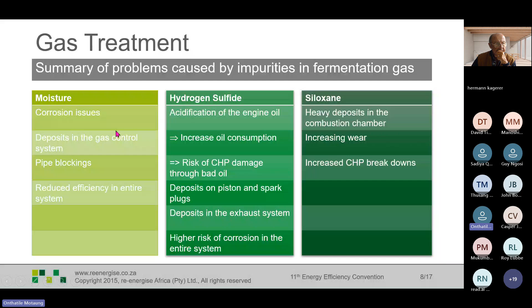This is one of the key elements we deal with daily on biogas plants: siloxanes, causing heavy deposits in the combustion chamber, as we've seen in the pictures, increasing wear of parts like bearings and turbocharger blades. The incrustation that forms on the cylinder or cylinder heads can score the inside of the cylinder, leading to increased breakdowns of the CHP, which is not desirable.